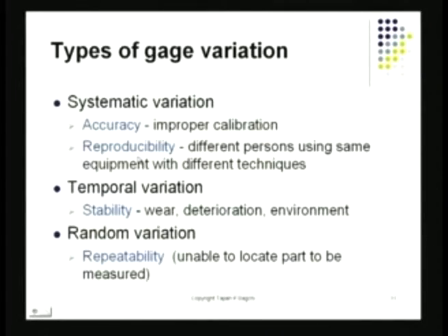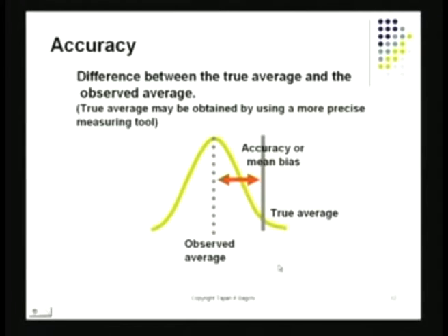This is a variance measurement. This is not an average measurement, it's a variance measurement. I also have a variance measurement when it comes down to repeatability, which is like repeat readings made with the same instrument. And of course, the issue of stability is also there, when the reading itself may change a little bit as time goes by. Let's try to get a good picture of what we are talking about.